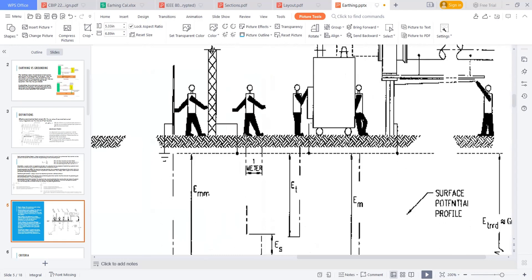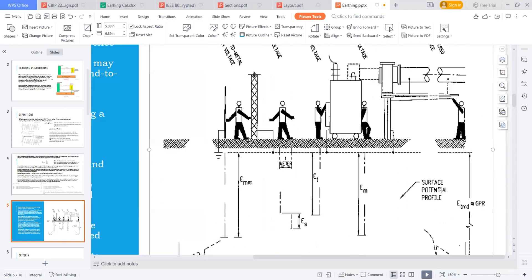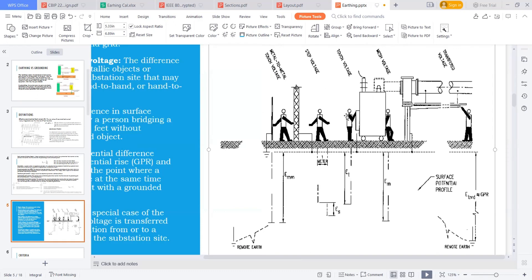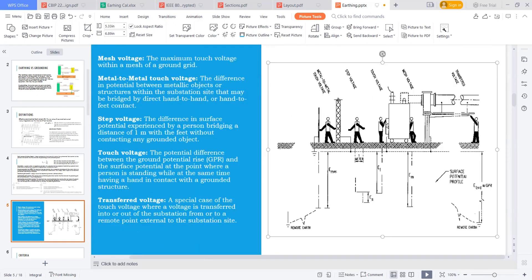So this is also a voltage developed — a voltage developing between two legs. Or else, the person touching any equipment — so this is a touch voltage. The potential difference between the GPR, which is the ground potential rise developed when the fault occurred, and the surface potential at the point where a person is standing and touching any grounded object. So the voltage is developing here — this is a touch voltage.